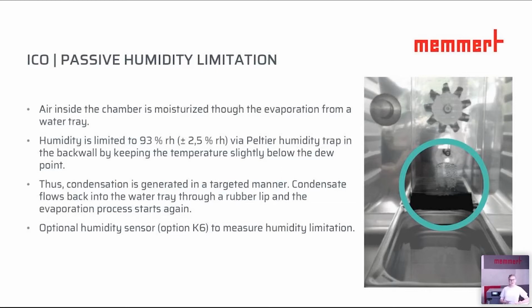So having a look at, first of all, the standard configuration, the passive humidity limitation. The air inside the chamber is basically humidified by a water tray, which you put inside. You fill it up with water, and due to the temperatures inside the chamber, the water evaporates and humidifies the interior. We are limiting this humidity to 93% by a humidity trap, which is located inside the back and basically simulates a dew point by keeping the temperature slightly below. The condensed water will then flow back to the water tray through a silicone rubber lip, and the evaporation cycle starts again. So this is a continual and uninterrupted cycle.